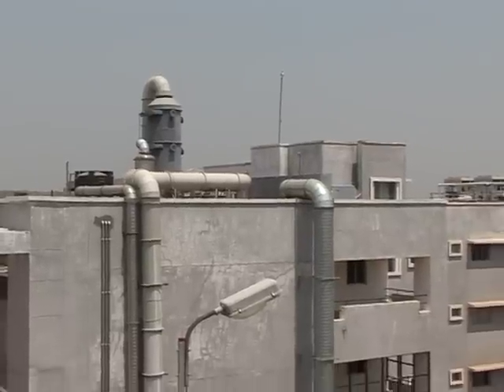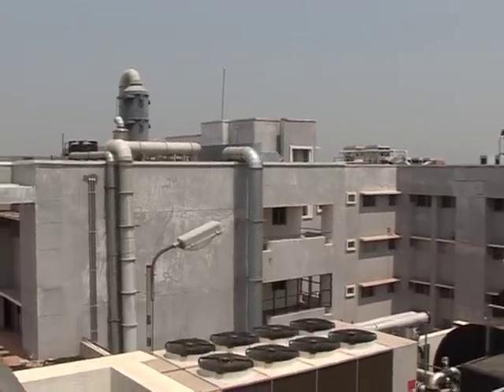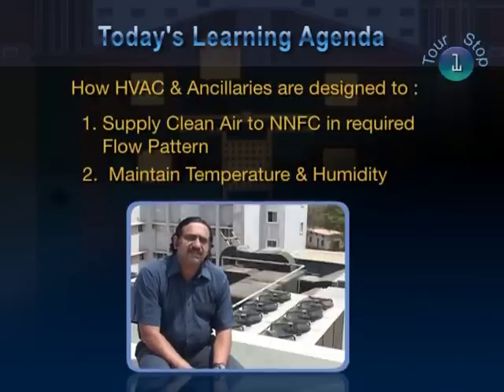We are starting this guided tour at this location because this is the heart of the clean room facility. This is the utility building, and behind me you see the HVAC system, which is located in this utility building, and behind me is the clean room facility. We will also discuss the air filtration system, the types of airflow within the clean room, and the fan filter units. We will also discuss how we can control the relative humidity and temperature within the clean room.